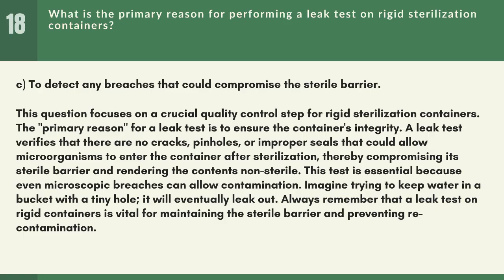This question focuses on a crucial quality control step for rigid sterilization containers. The primary reason for a leak test is to ensure the container's integrity. A leak test verifies that there are no cracks, pinholes, or improper seals that could allow microorganisms to enter the container after sterilization, thereby compromising its sterile barrier and rendering the contents non-sterile.